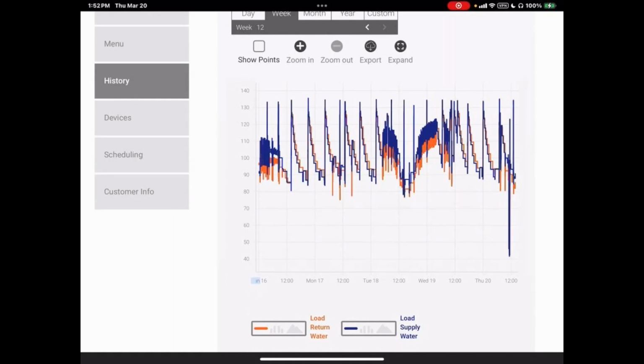But is there ever a situation where you could go into a prolonged domestic hot water call and not come back into space heating? Let's say a failure, it could be literally a leak. You're just running water through the tank. You can't really satisfy that domestic water call. Does the firmware have some type of an override after 30 minutes, 60 minutes, something like that? It does not currently. This is the same strategy that we've been using since 2017.